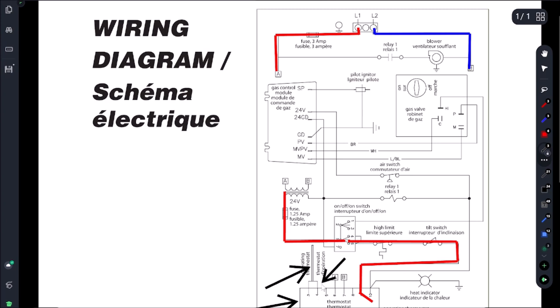So an easy way to test it is we're going to go see if we have power on pin 9 and if we have power on pin 9 but we don't have power in pin 10, we're going to do an ohm test on this thermostat. If the ohm test passes we need a board, and in this case I think we're going to need a board but let's go through the troubleshooting.